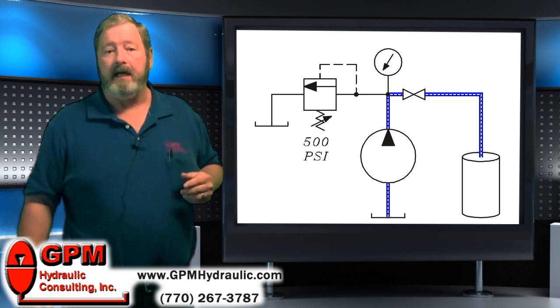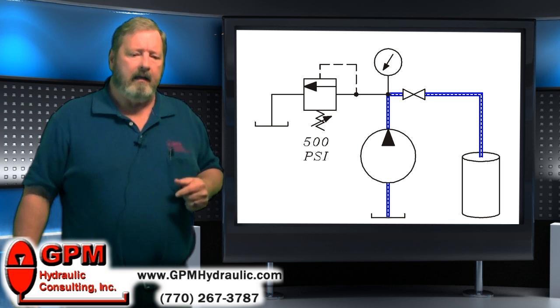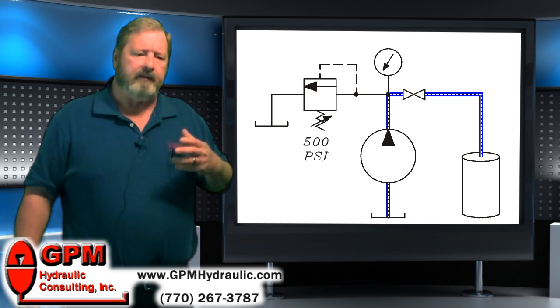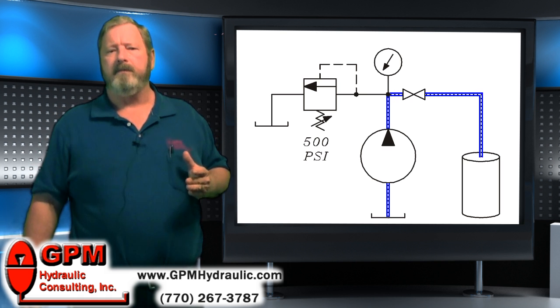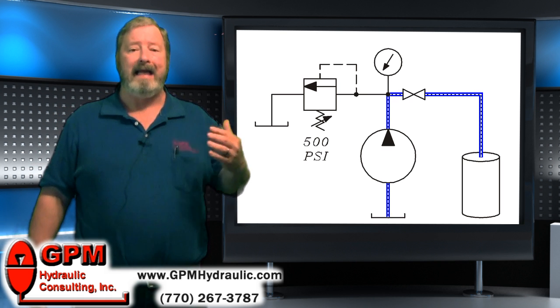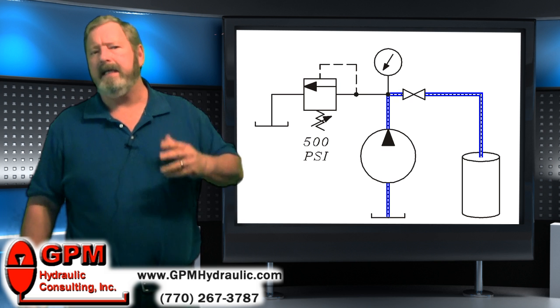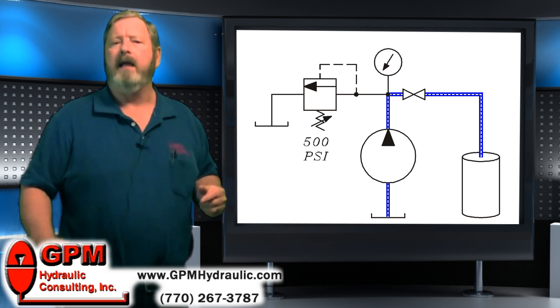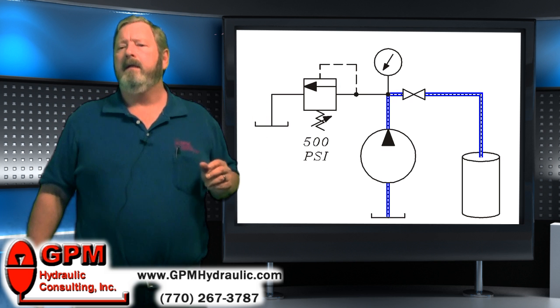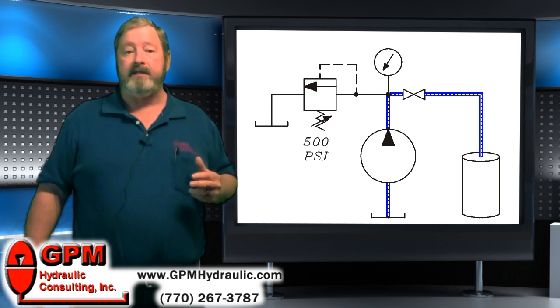And what pressure do we read on the gauge? Well, if you said zero, you're right again. There is a little bit of resistance with the friction of the pipes, overcoming gravity and whatnot. But for all practical purposes, there is no resistance and the gauge would read zero. So does that mean that I need to change my pump? Well, of course not. A brand new pump would perform exactly the same way, would it not?